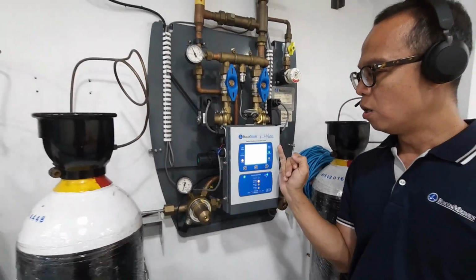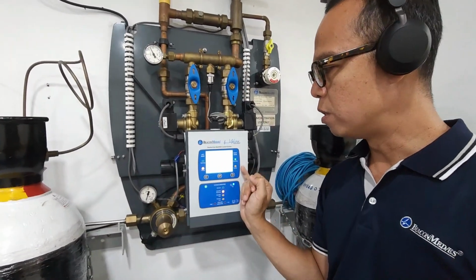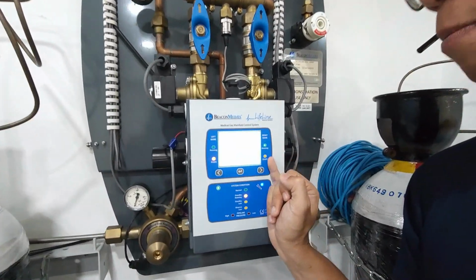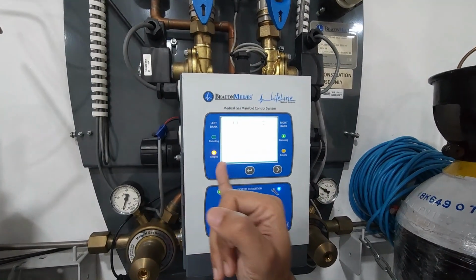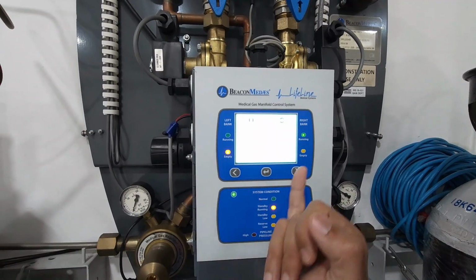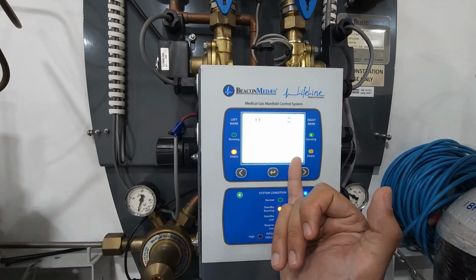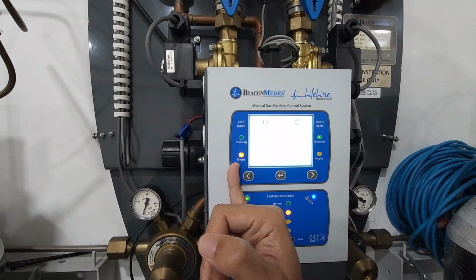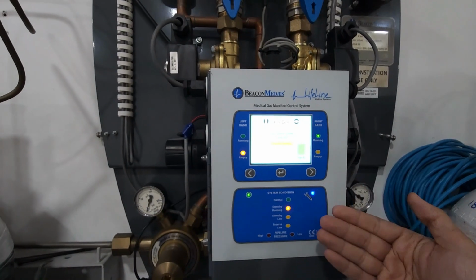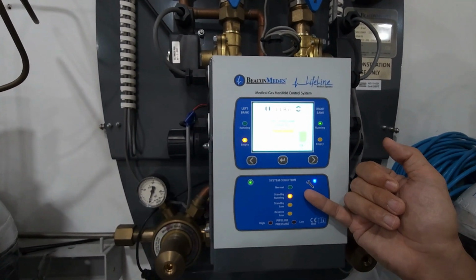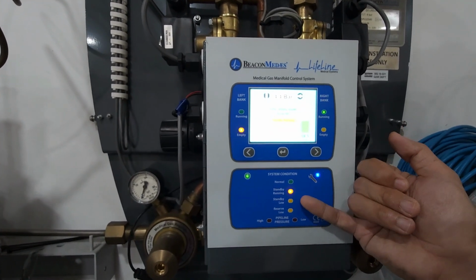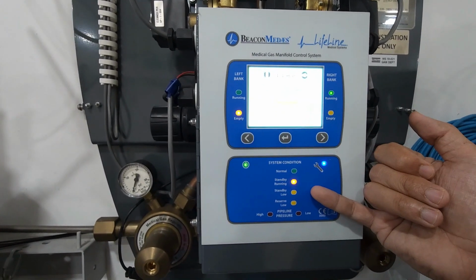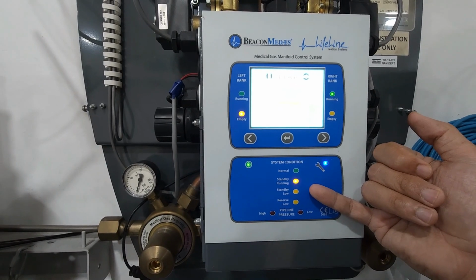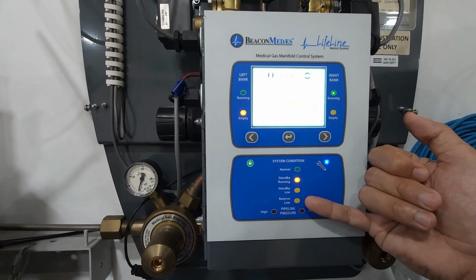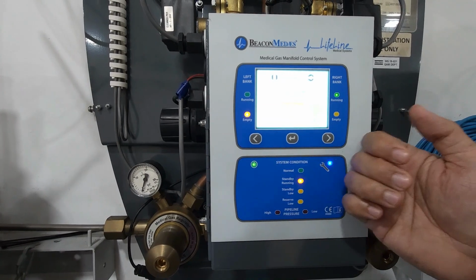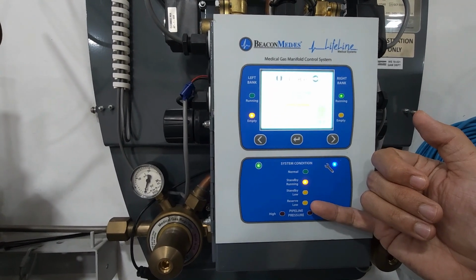On the right and on the left of the screen, of course, there's a simple LED light that says running or empty. So you can see the difference there, empty, running. In case the screen doesn't work for whatever reason, you still have those LED lights as a redundancy system. And at the bottom here are also the alarm signals for standby running, standby low, and reserve low according to the HTM standards of alarms. On the reserve low, if you don't have any ERM connected to this panel, this is not being used.